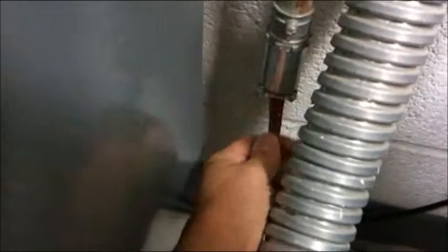Today I have to finish piping this 3/4 inch pipe up to the ceiling and attach the wire that goes to the art room for the kiln. We also have to hook up a ground wire. Basically what we're going to do is tap off this ground right here. As you can see, we're going to tap off with a bug, and we're going to come in and feed this transformer somewhere over here. 1/2 inch knockout, go in there, and we have to ground it to this ground lug right here. That's to keep the voltage stable so it doesn't fluctuate. The transformer has to have a ground in it. Okay.